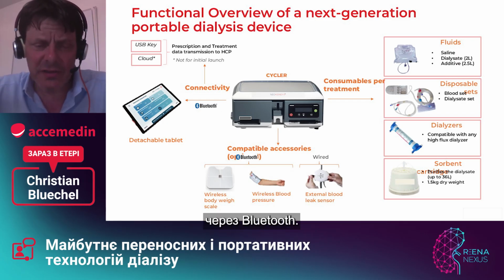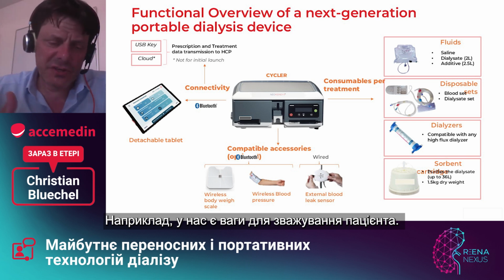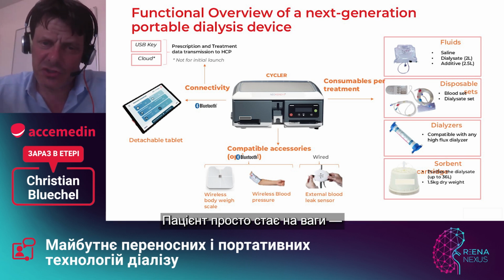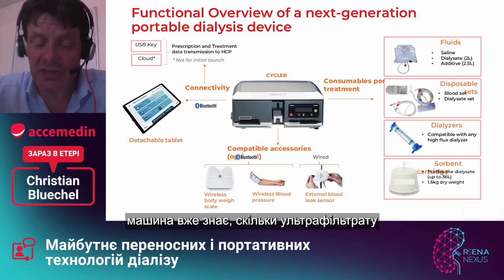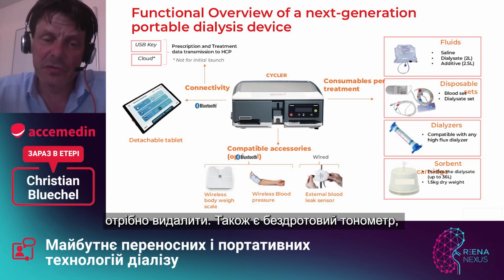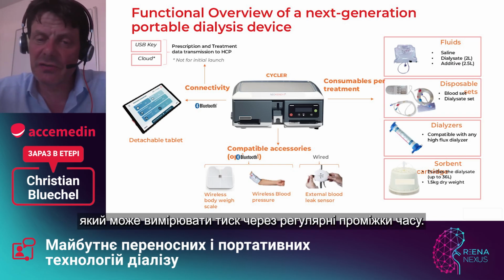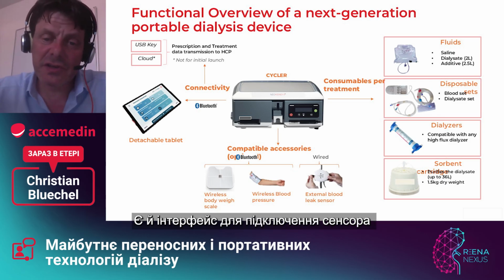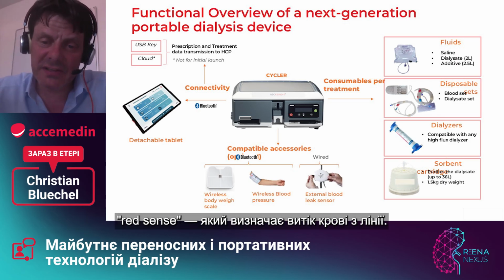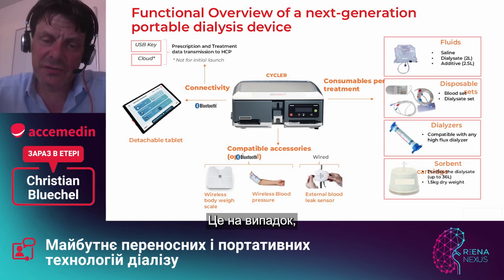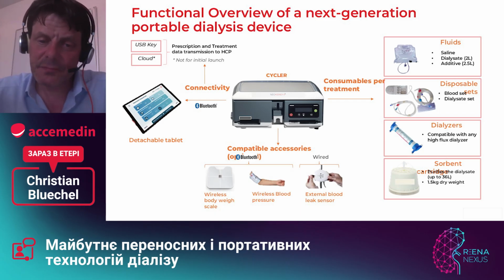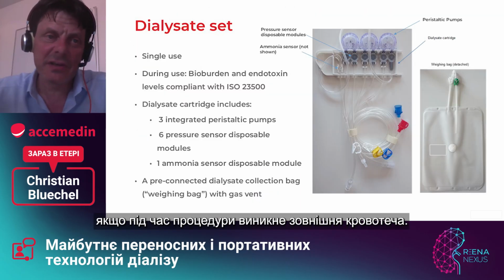There's a body scale. So the patient steps on the weighing scale, and then the machine already knows or proposes how much ultrafiltration has to be removed. And there is a wireless blood pressure sensor which can monitor at regular intervals. We also have the interface for the red sense disconnection sensor here, in case there's an external blood leak.